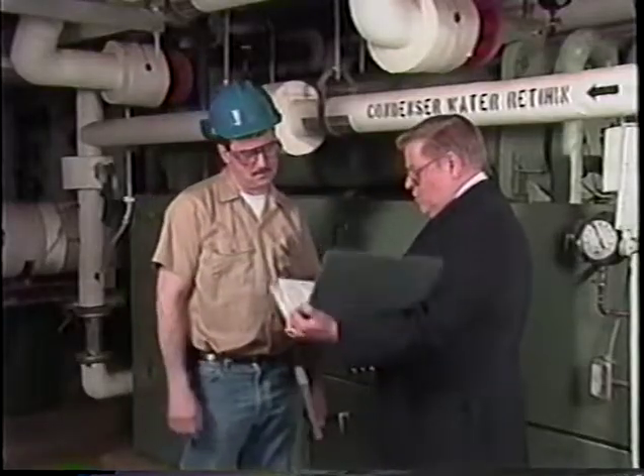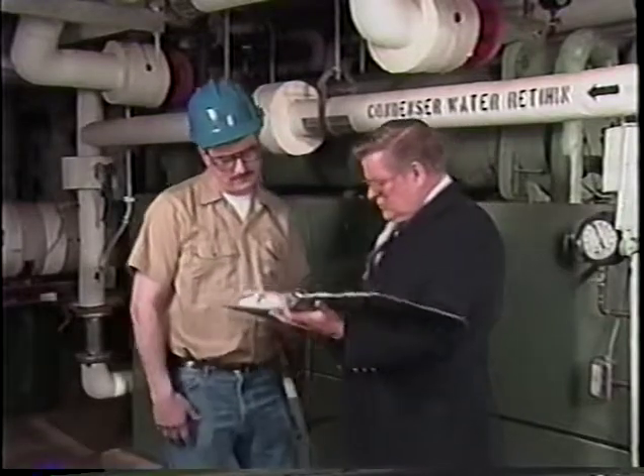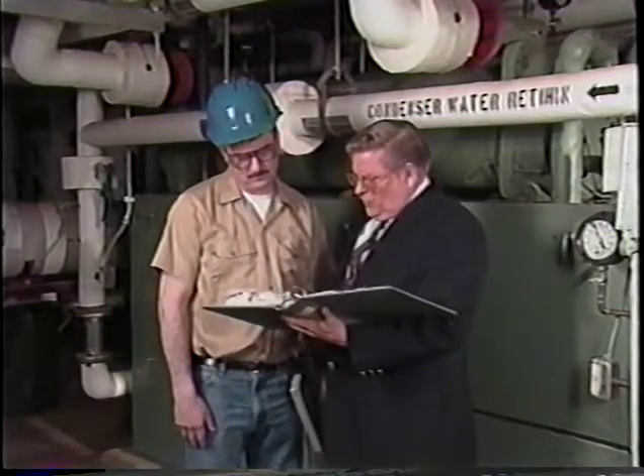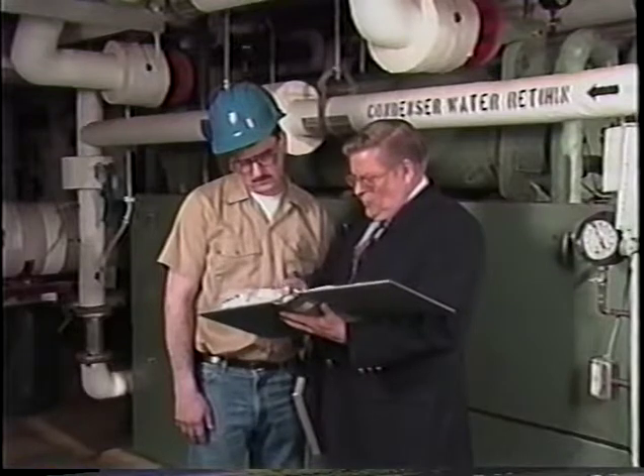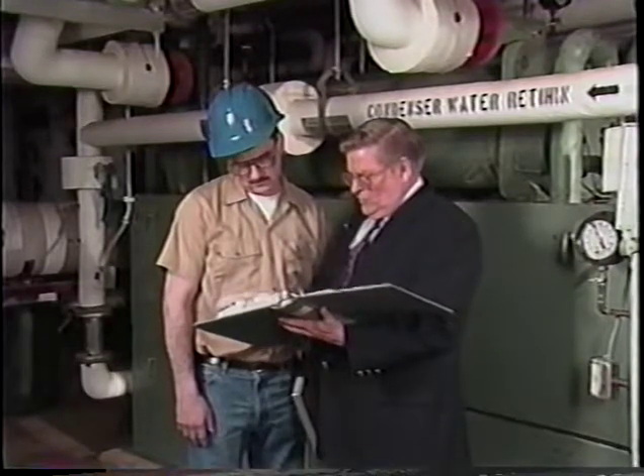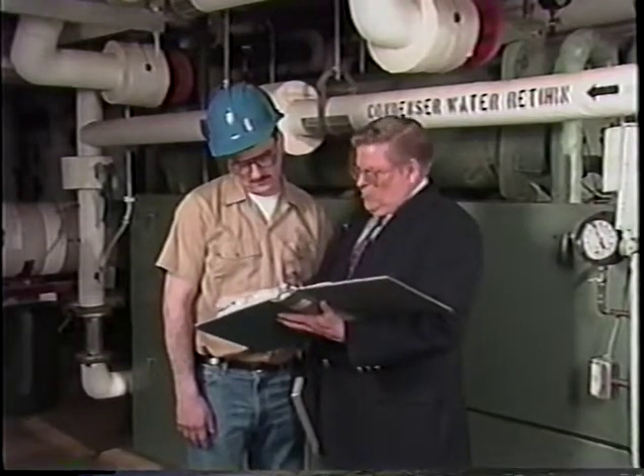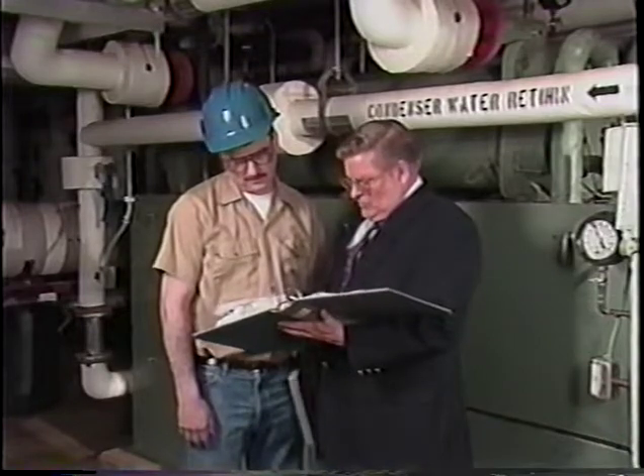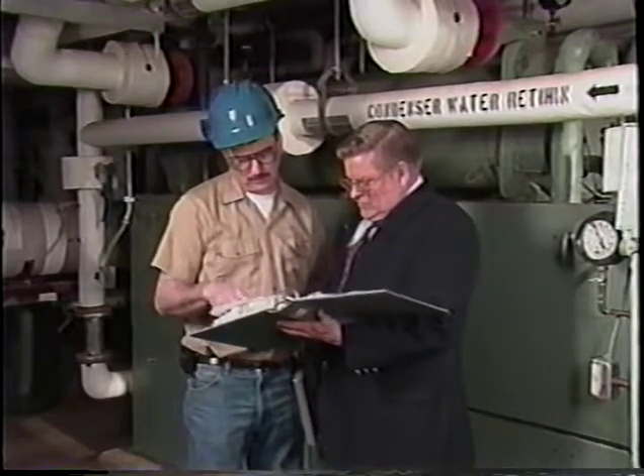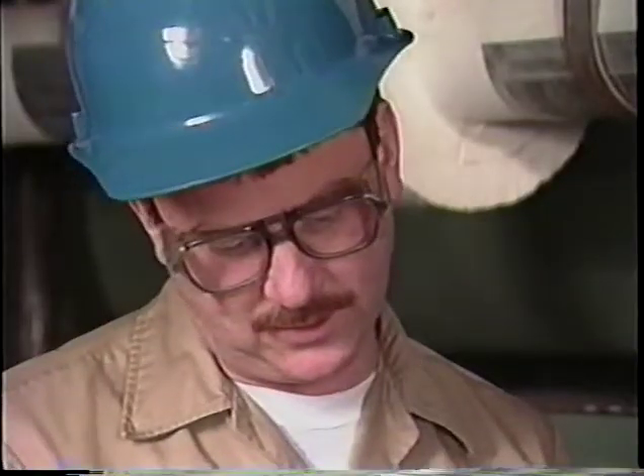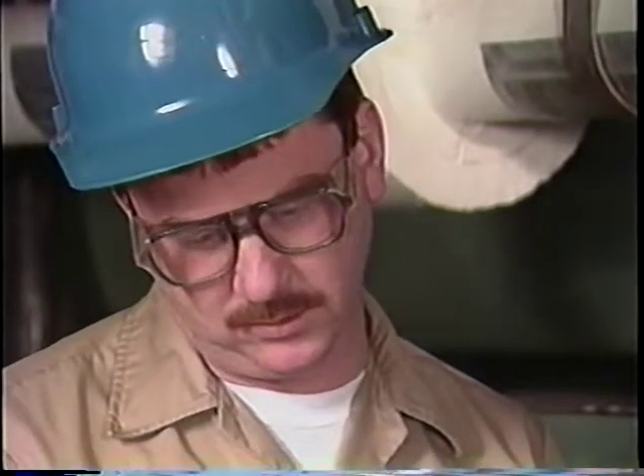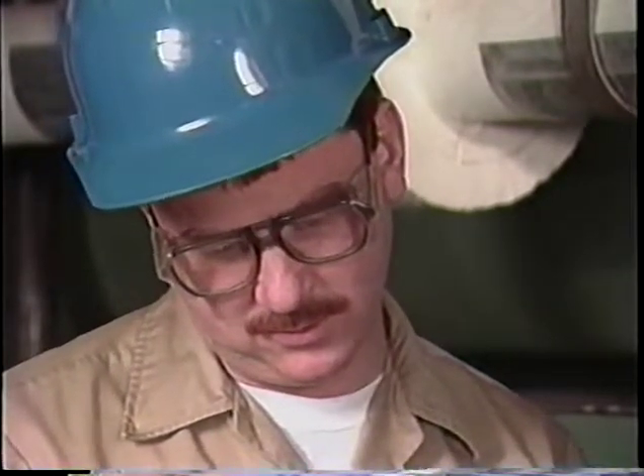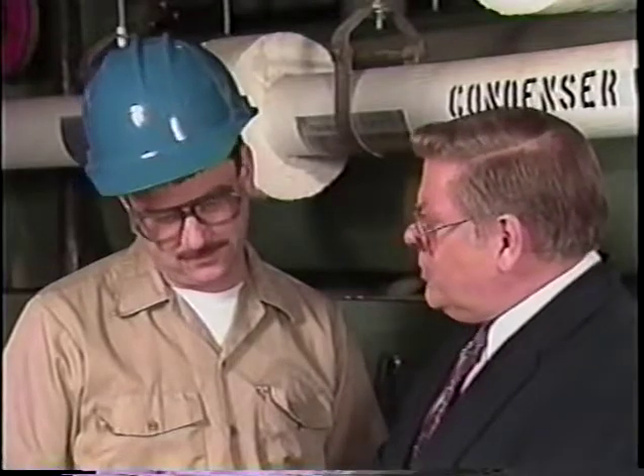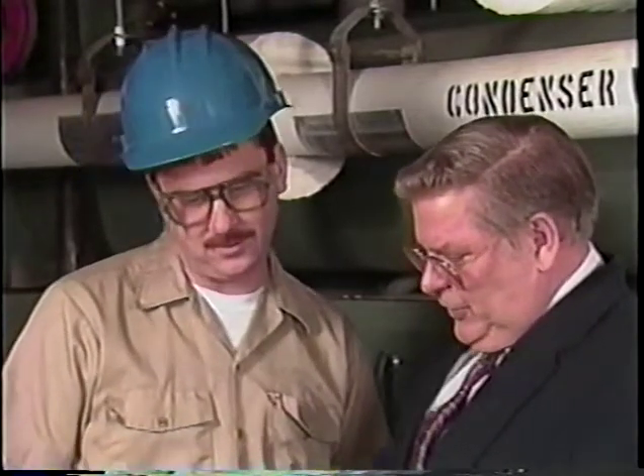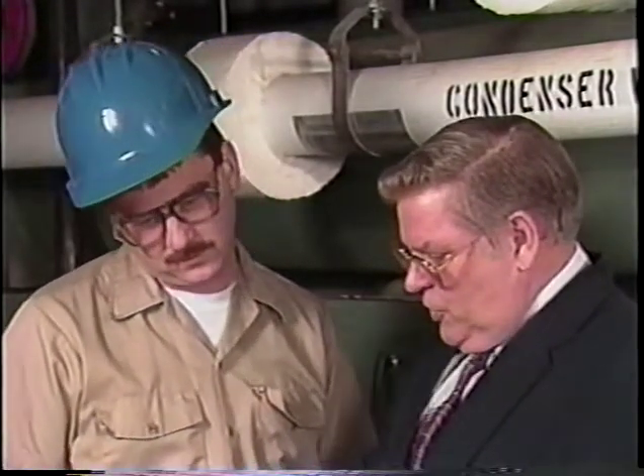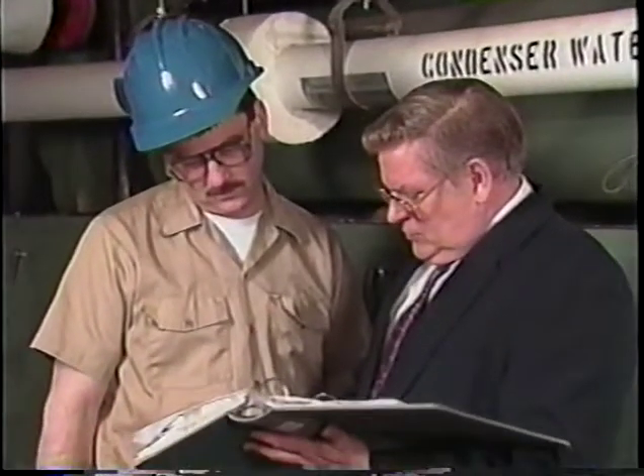You should be able to find past log sheets on the job site. If no log exists, then a log sheet should be started. When starting a new log sheet, you will need to record the design conditions of the chiller. This design information should be available either at the job site or from the manufacturer's representative, such as the local distributor or dealer's office. If you cannot get design data, then use the data taken on the initial startup of the chiller as a reference.